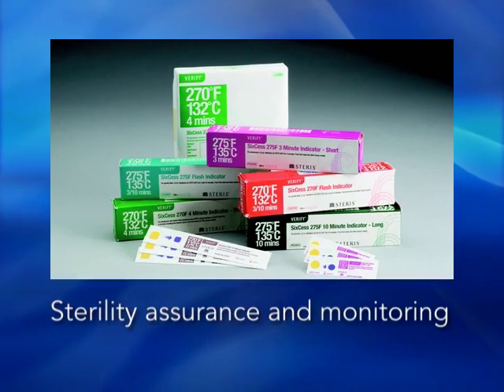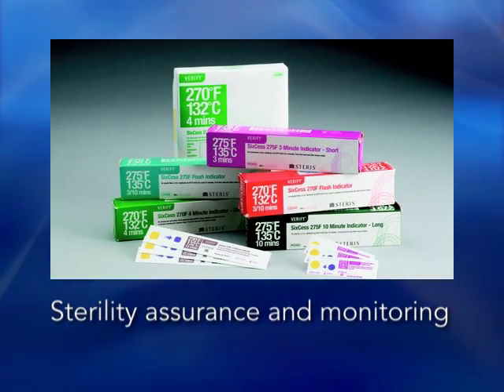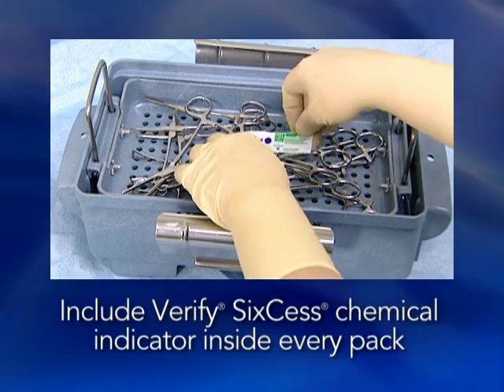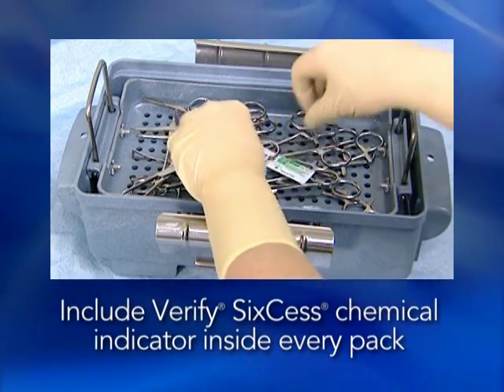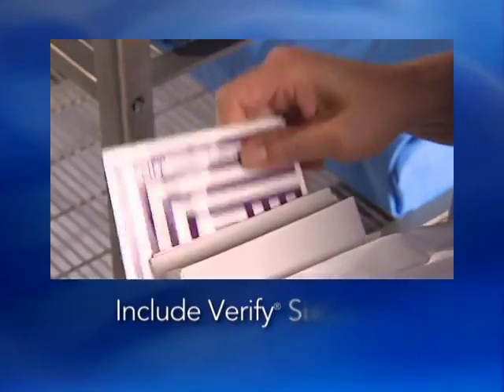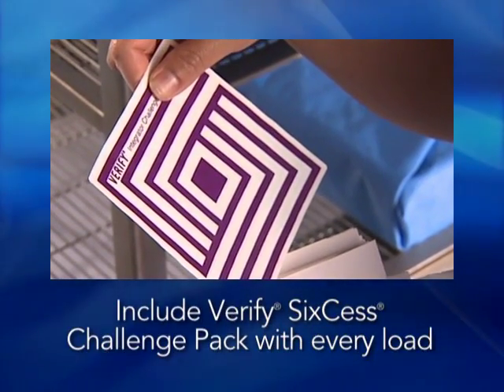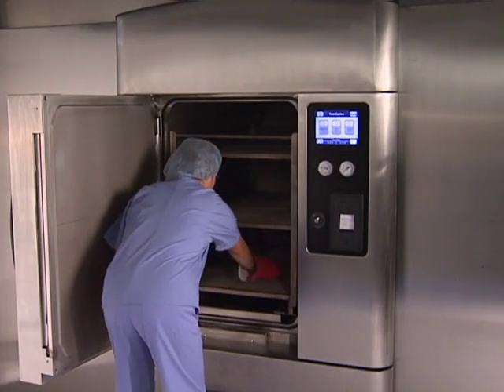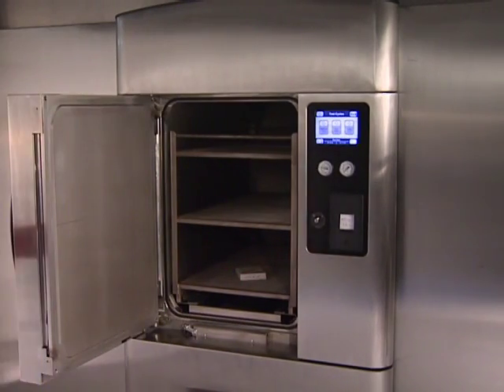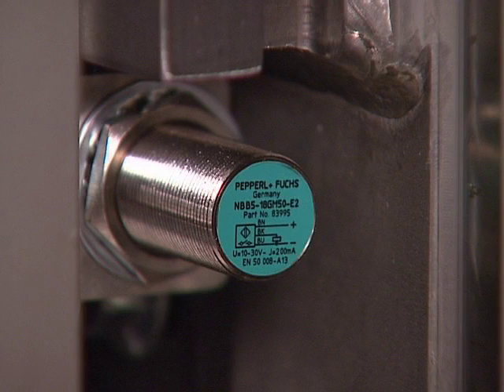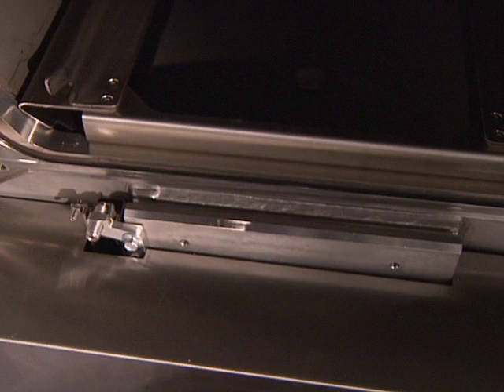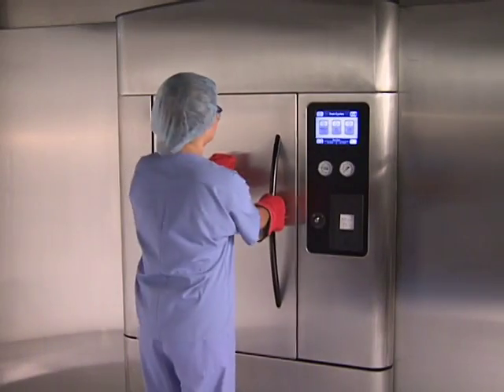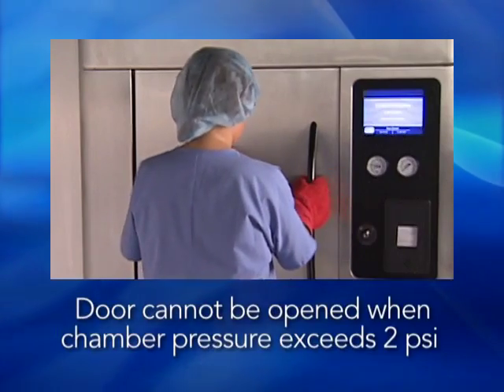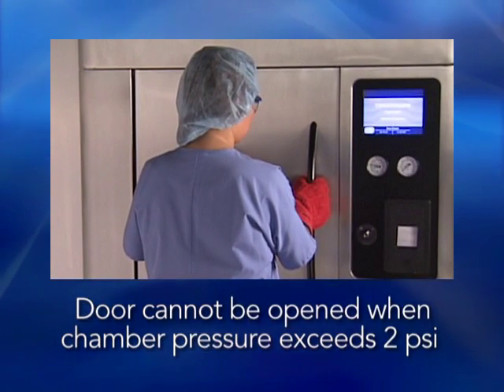Sterility assurance and monitoring is a key part of the sterility process. For pack and load control, STERIS recommends you insert a Verify SixCess chemical indicator inside every pack and a Verify SixCess challenge pack with every load. Place the challenge pack on the bottom shelf of the loading car, directly over the drain, and then close the chamber door. A proximity switch is used to determine if the door is closed. An additional seal pressure switch prevents inadvertent cycle initiation if the door is not sealed. As long as the seal is intact and energized, and there is more than 2 psi pressure in the chamber, the door cannot be opened.